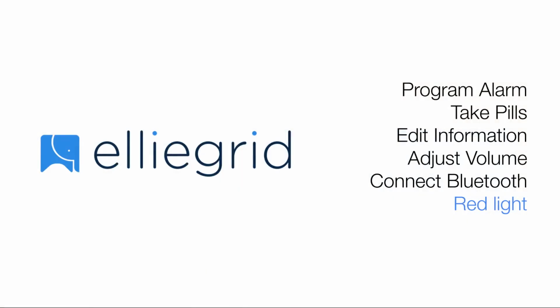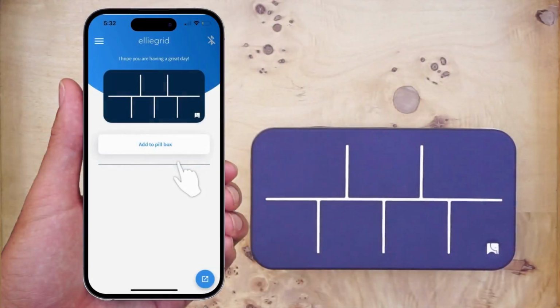Red light. If there is a red flashing light on the pillbox, this means that the device's internal clock is incorrect. This will occur if the battery runs out completely or if some sort of error occurred causing the device to restart. The alarms will not go off when they are supposed to if the device is in this state.